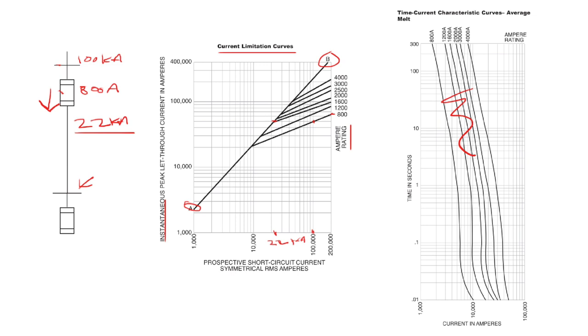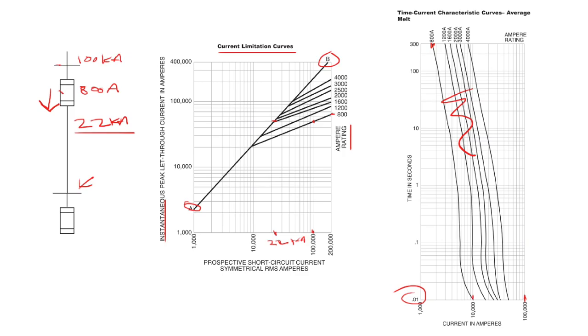So if we had 100,000 amps fault current and this is our 800 amp fuse, we can see that the 100,000 amps exceeds the instantaneous trip time. So in a little over half a cycle, this fuse is going to melt, and prior to that it's going to let through around 22,000 symmetrical amps of fault current.